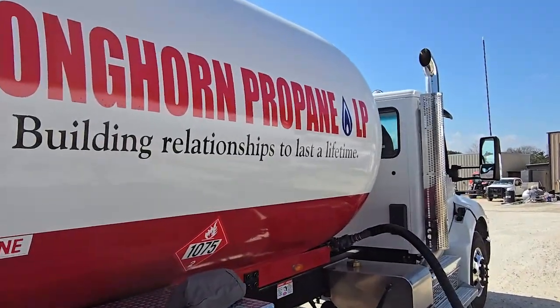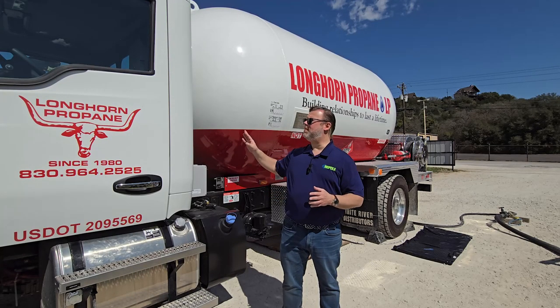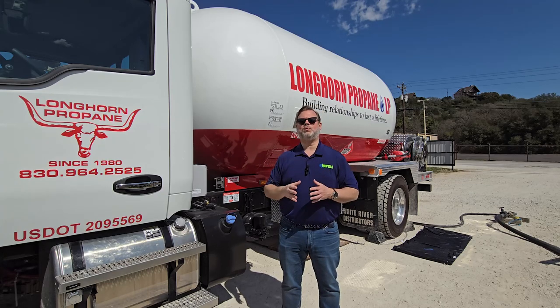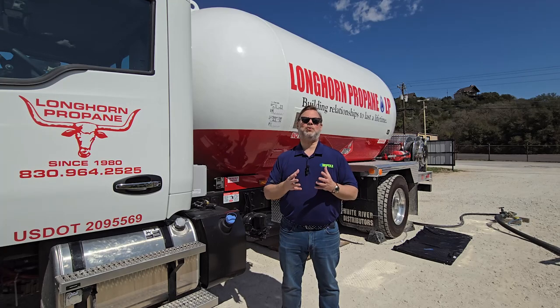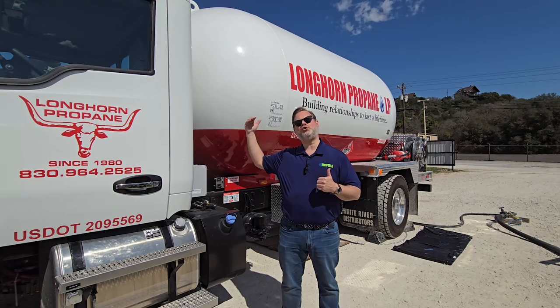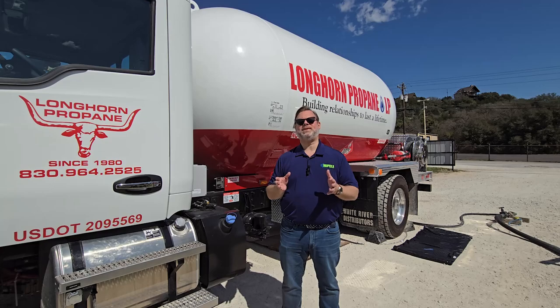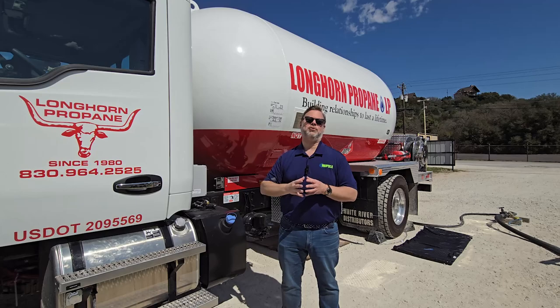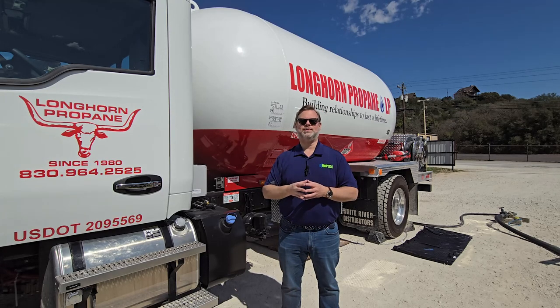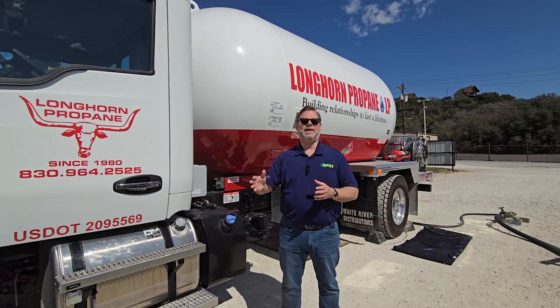You may be asking yourself, why do you need the Mopeka Transport Solution? We're all well aware that within the industry, whether it be bobtails or long haulers, there are certain limitations with traditional floats and gauges. In the past, a traditional float and gauge has an inaccuracy between 5 and 10 percent, and therefore what we've historically been doing is short filling our vehicles. With the Mopeka Transport Solution, we can take that inaccuracy down to plus or minus 1 percent, maximizing your load without violating DOT regulations, and tracking every single last drop coming out of that vehicle throughout the day.